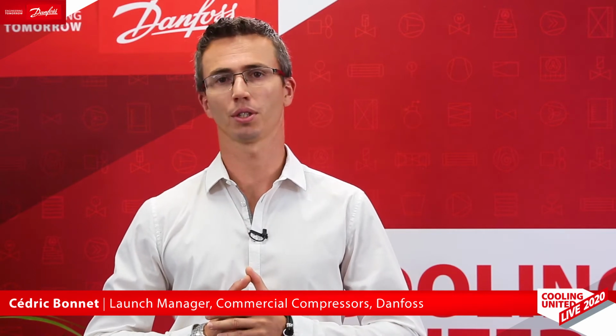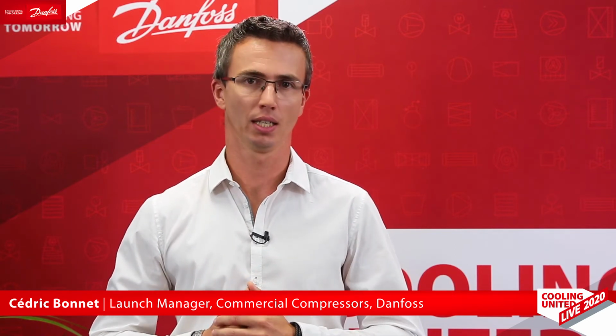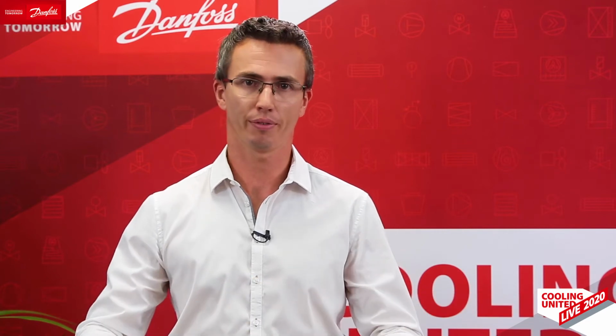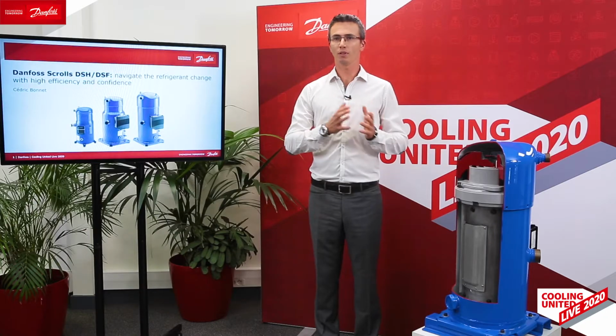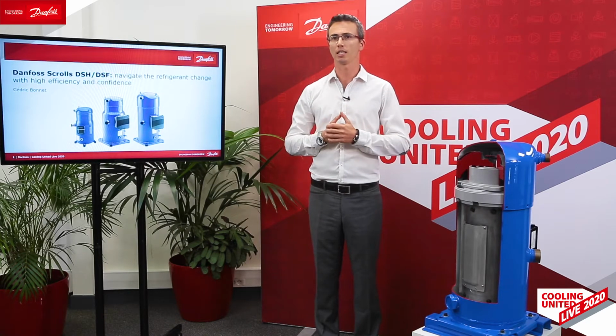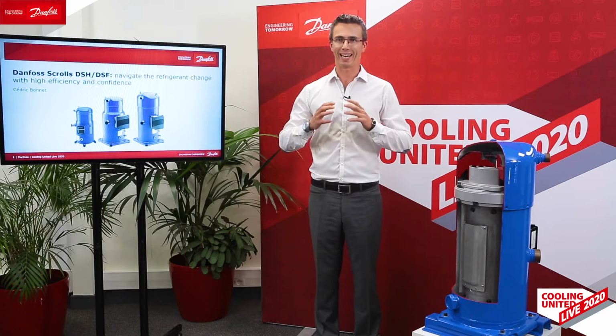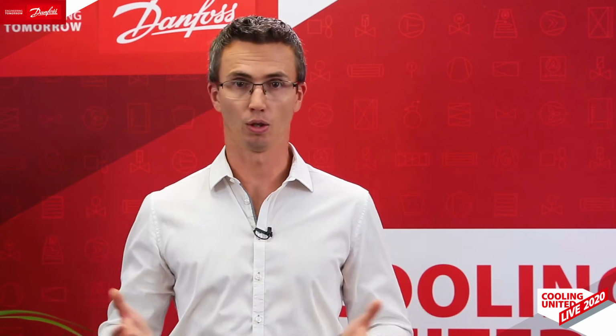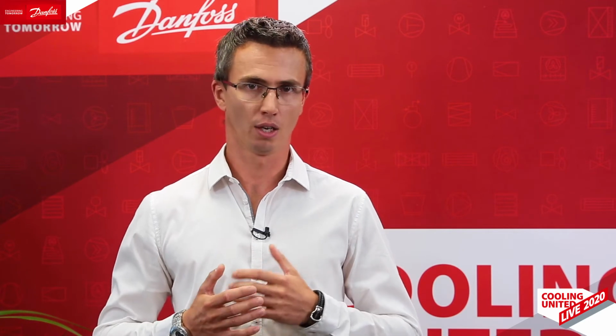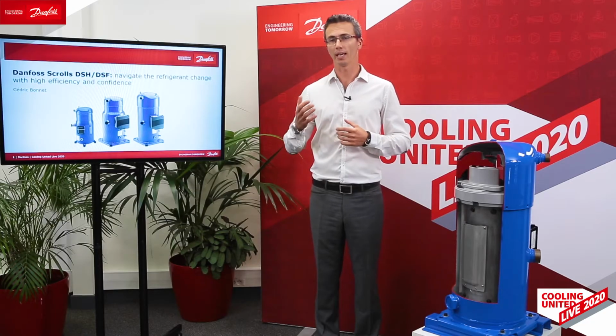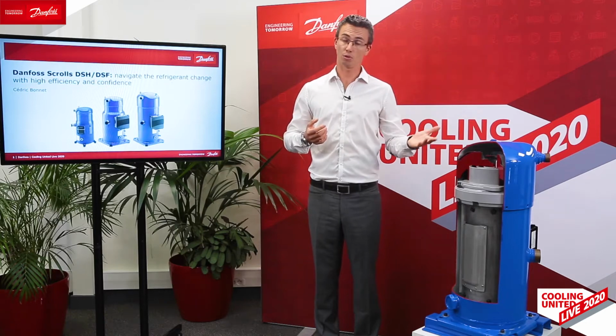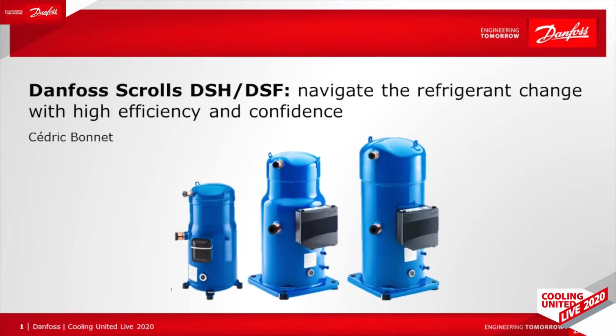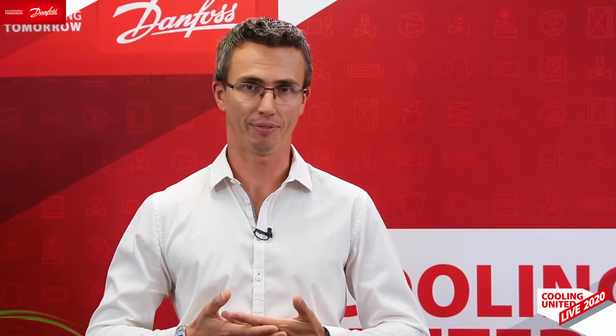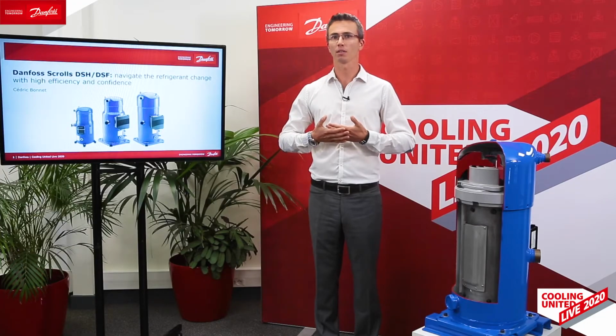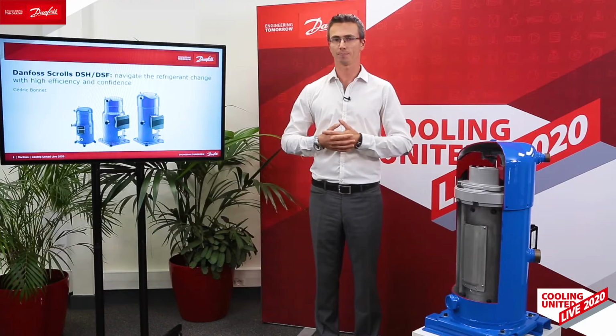And I'm here today to present you our DSF and DSH ranges and to show you how it helps in the refrigerant transition. From 7 to 44 ton, these two ranges have been fully qualified for high seasonal efficiency with a wide operating map without liquid injection for applications of rooftops, air-cooled chiller, water-cooled chiller, for cooling only and for reversible systems. And I don't forget, on top of these ranges for A2L, our DSH 50 ton, which is our largest compressor for larger air conditioning systems.